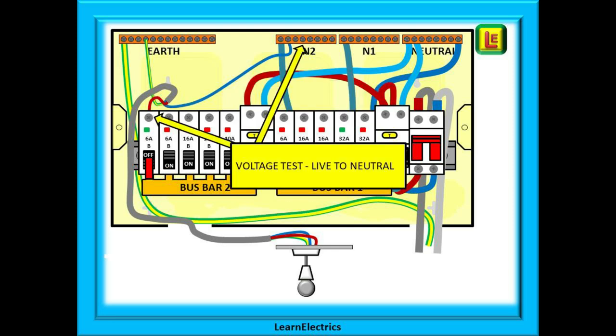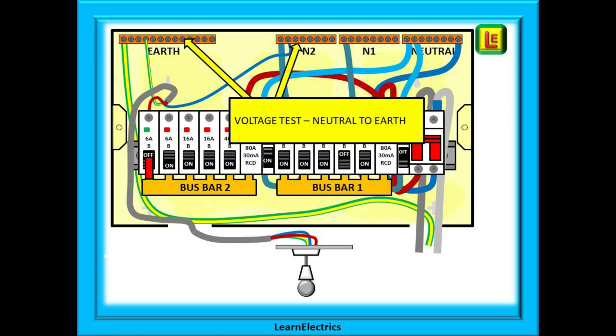Now a voltage test between the MCB live, the load terminal and the neutral bar. If this is a split load board, then make sure that you are testing to the correct neutral bar as each RCD will have its own neutral. And finally test neutral to earth. We are looking for zero volts to be shown in each of the three tests. Anything else is a problem. Check your circuit identification and locking off if you need to and retest. Until all three combinations read zero volt, then you are not properly isolated from the electricity.